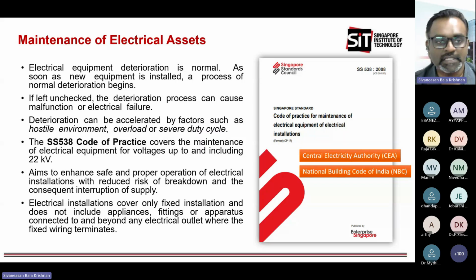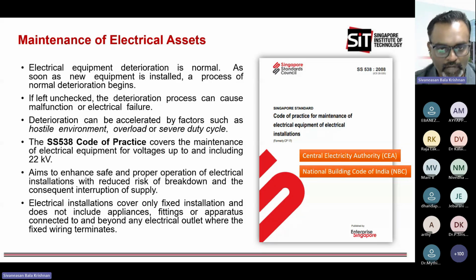Hostile environment, for example within a substation, or overloading, can cause a severe duty cycle with too large on and off operation. Even recently there was discussion about issues in the electrical rail network in Singapore, where transformers are switched off during the night and turned on in the day. This is not something we should do, because the duty cycle creates a severe inrush current during turn-on periods, which we don't want to subject transformers to.